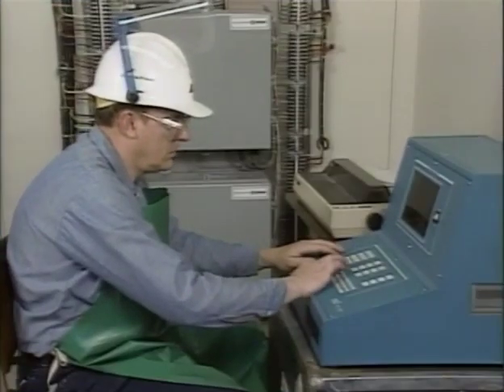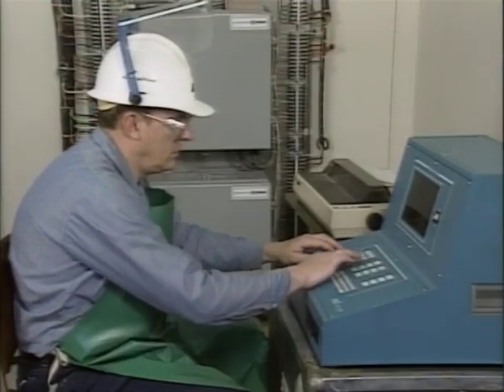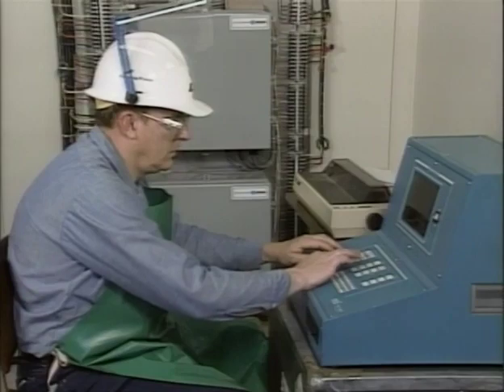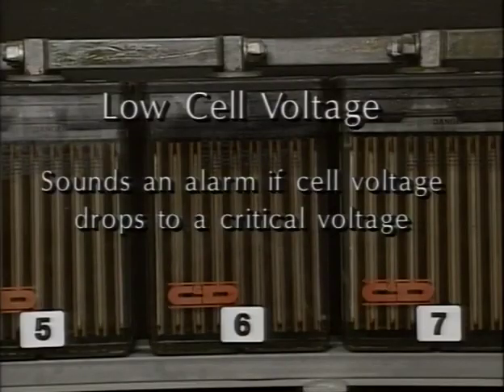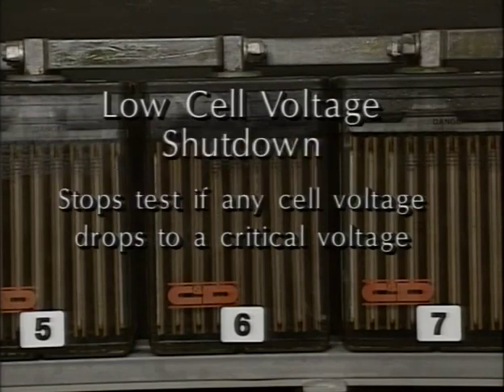The control unit is also programmed for a variety of alarm and cutoff values. Some of these may include low cell voltage, to sound an alarm if any cell drops to a critical voltage, usually 1.75 volts. Low cell voltage shutdown, to stop the test if any cell voltage drops to a critical voltage at which the cell could reverse its polarity. This is usually 1 volt.